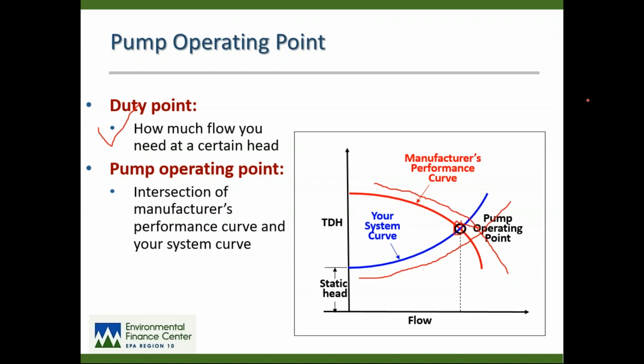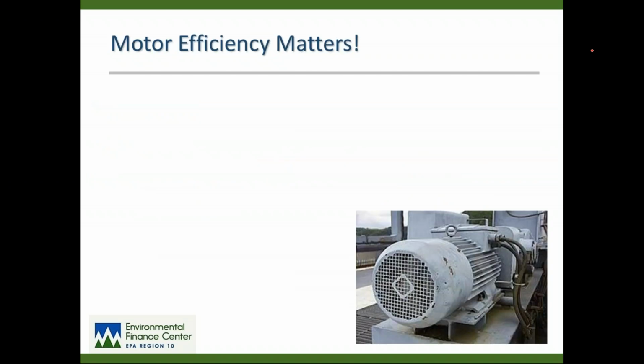And again, we do a full 6-hour in-person workshop on optimizing pump curves. And this is kind of the 30,000 foot elevation. And I just wanted to mainly get you familiar with some of these terms, when you start getting out your manufacturer's curve and you start looking at your own hydraulic modeling, and you actually get into the nuts and bolts of doing an energy audit.